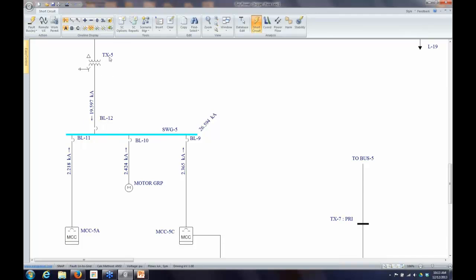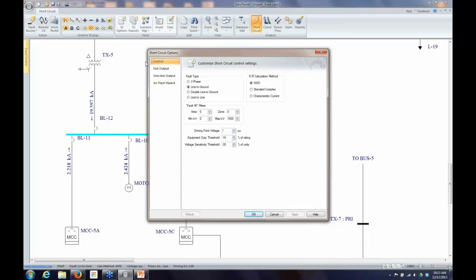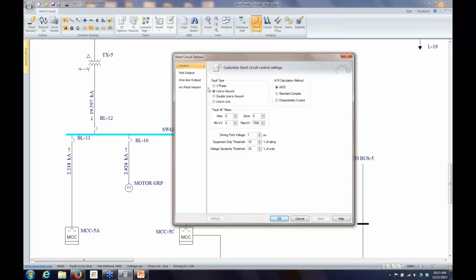If we go into short circuit options, there are four categories. The first is called Control, and the fault type here matches what I have on screen — just two different ways to set it. The Fault All Filters option lets me automatically filter what I'm faulting, either by bus area and zone — which is an EasyPower concept for segregating your system into different groups — or by voltage level, so I could fault only 480-volt buses by setting the minimum and maximum kV range.